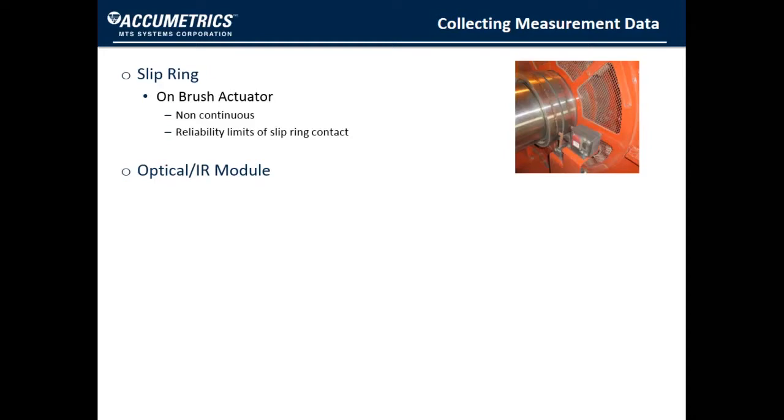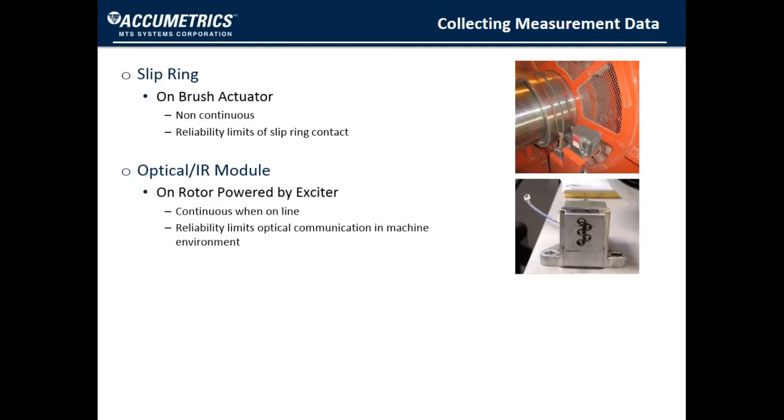Another method is an optical or infrared module that is mounted on the rotor. This is an electronic circuit that is powered when excitation comes on. So it is continuous when the unit is online, but it is not operational before you turn excitation on. Its limitation is the reliability of the optical communication.